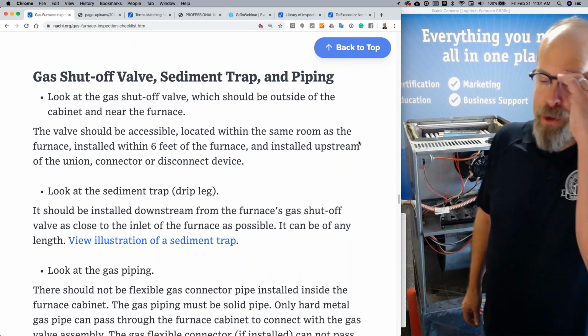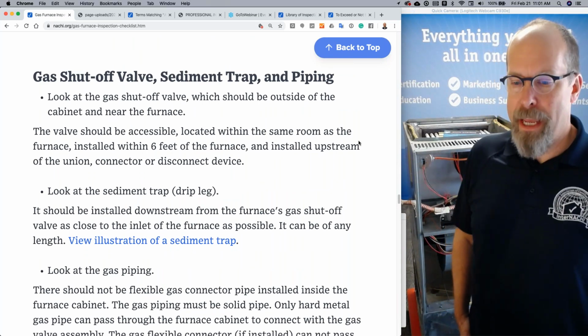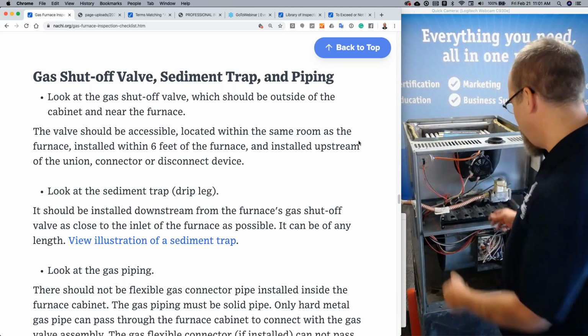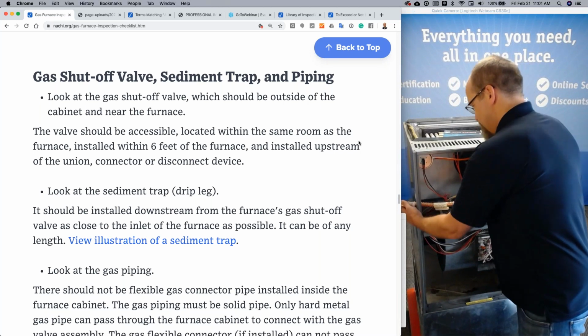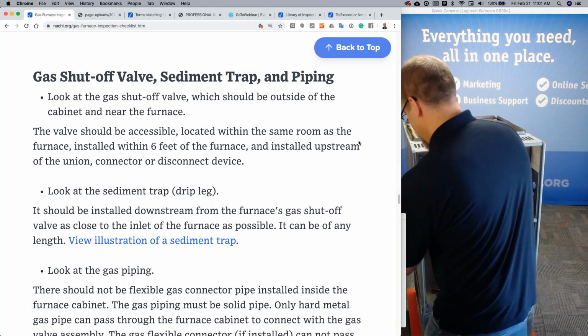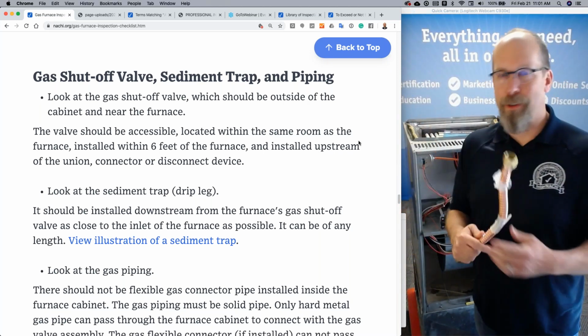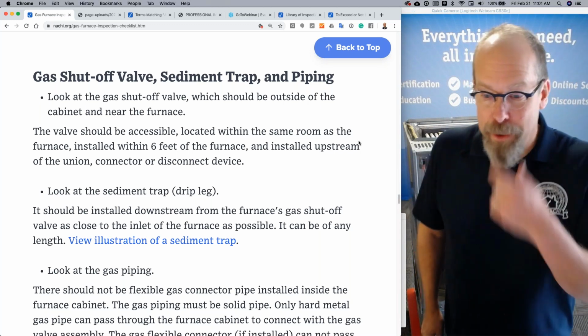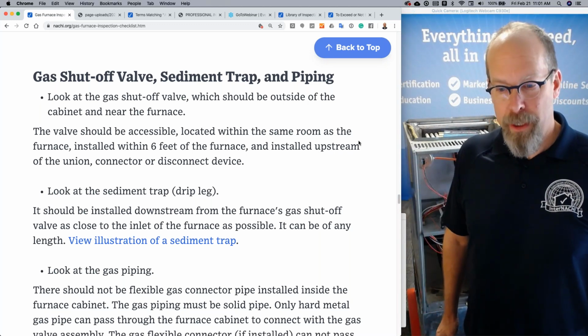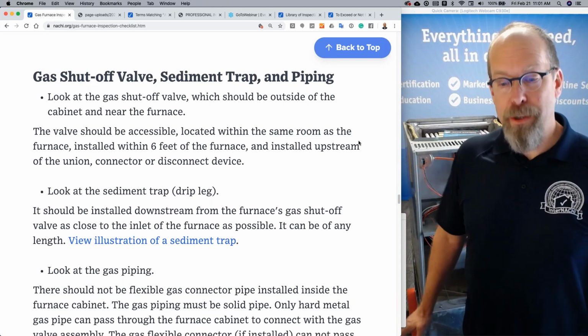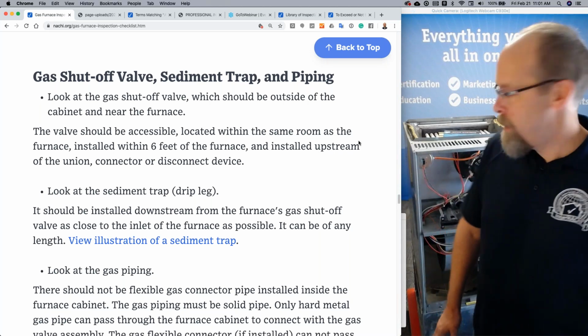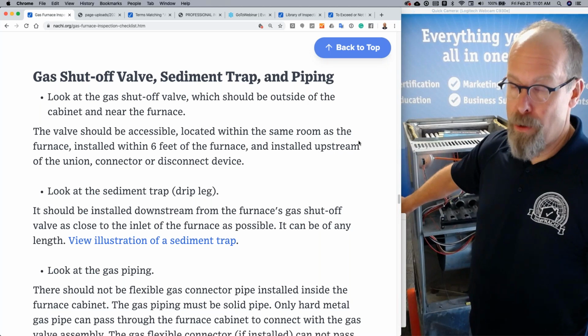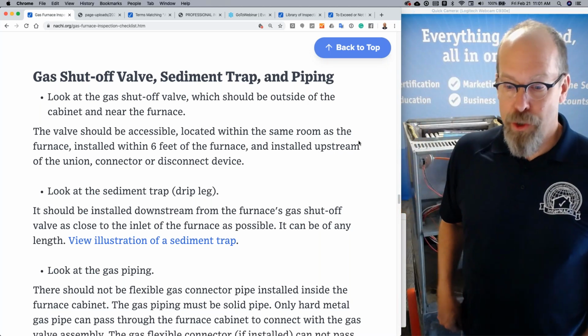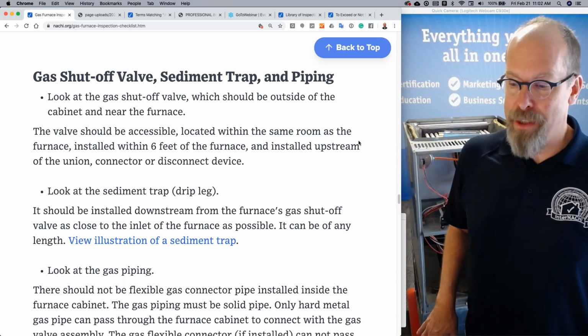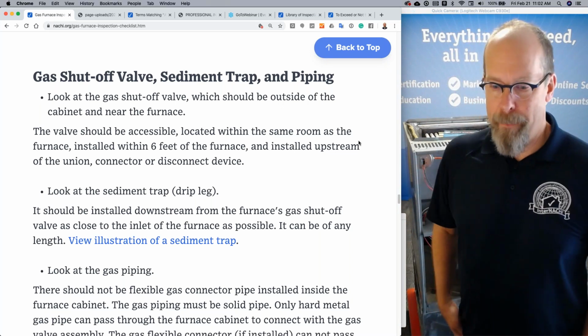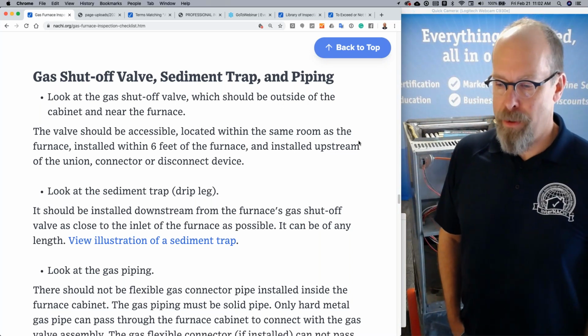Gas shutoff valve, sediment trap, and piping. Look at the gas shutoff valve, which should be outside of the cabinet near the furnace. So it should be right here, right? And actually, I'm just teasing you. This pipe is for water, so it's for water use only. The valve should be accessible, located within the same room as the furnace, installed within 6 feet of the furnace, installed upstream of the union, connector, or disconnect device. So it should be right here. Look for a sediment trap or a drip leg, which is just below it. It should be installed downstream of the gas shutoff valve. So if the valve was right here, below it is the sediment trap, as close to the inlet of the furnace as possible. And it can be of any length.